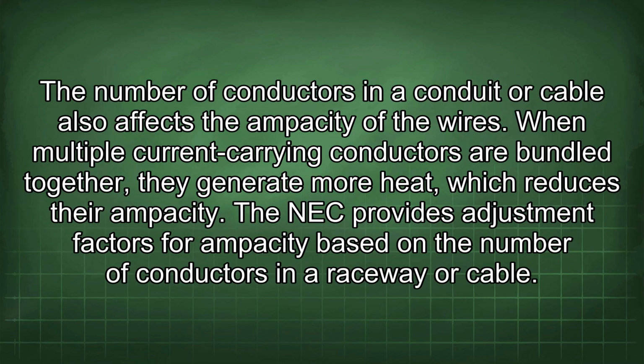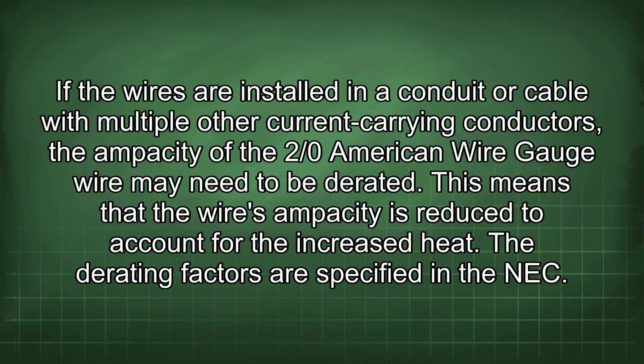The number of conductors in a conduit or cable also affects the ampacity of the wires. When multiple current carrying conductors are bundled together, they generate more heat, which reduces their ampacity. The NEC provides adjustment factors for ampacity based on the number of conductors in a raceway or cable. If the wires are installed in a conduit or cable with multiple other current carrying conductors, the ampacity of the 2/0 American wire gauge wire may need to be derated. This means that the wire's ampacity is reduced to account for the increased heat. The derating factors are specified in the NEC.